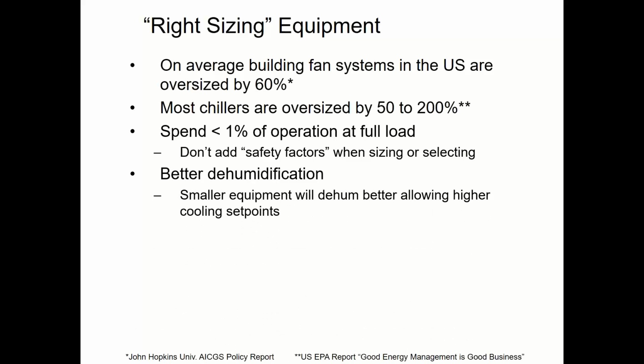On the cooling side, it's even more important than on furnaces and boilers. If you oversize the cooling, it will be a dehumidification problem for the building. Your system only dehumidifies when the compressor is running. It sends cold refrigerant to the indoor evaporator coil. That coil lowers the temperature of the air coming through it until it gets down to the dew point of the air. Then it can start pouring moisture out. It takes a few minutes to do that. It has to run 4, 5, 6 minutes before it hits the dew point and hence dehumidifies.